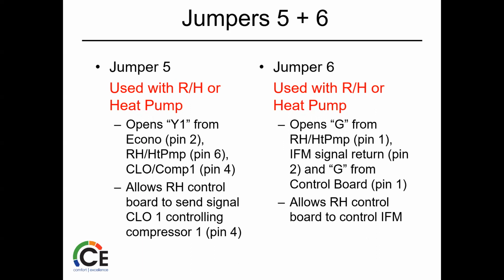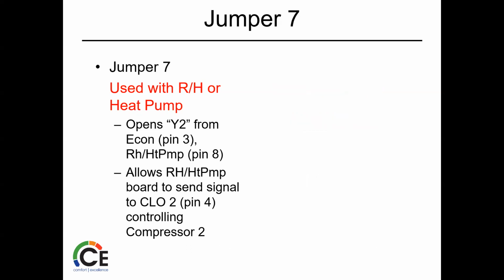So jumper 5, again, opens Y1, allows the reheat control board to send signal to CLO controlling the compressor. So that's why we cut those if we're using that. Jumper 6 has to do with the fan, indoor fan motor, signal and return. And then jumper 7 is just the second stage of that.